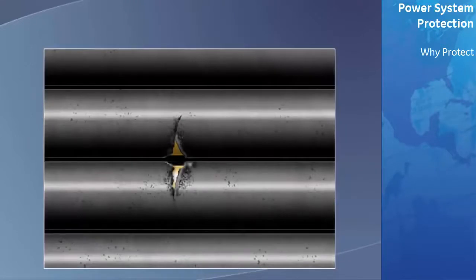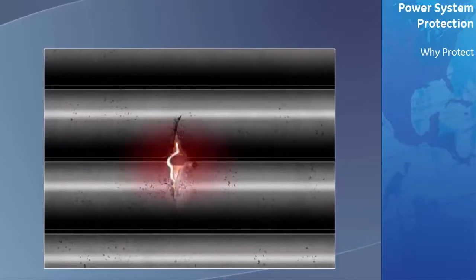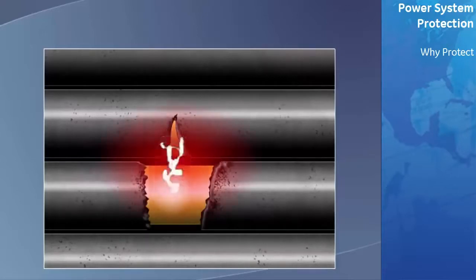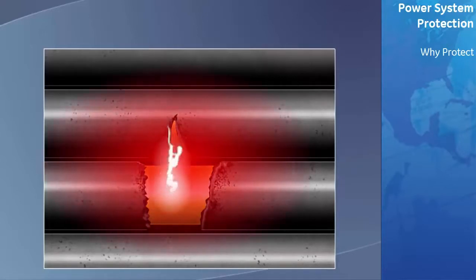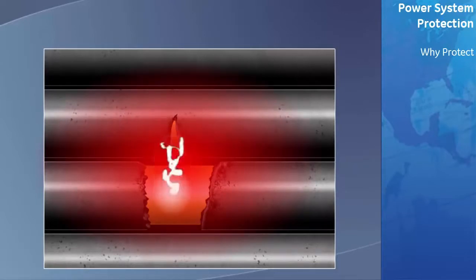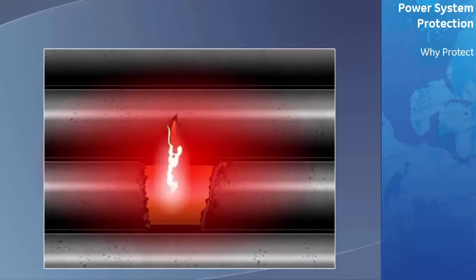If the fault isn't isolated quickly, the fault current will cause the conductors to heat. As the temperature of the conductor rises, the damage will spread to the surrounding insulation, causing it to fail, and the fault current will increase even further. As the level of fault current increases, the temperature will rise to a level that will melt the conductors and burn the steel laminations, resulting in catastrophic damage to this inadequately protected transformer.